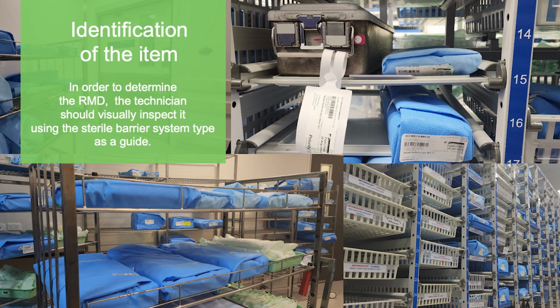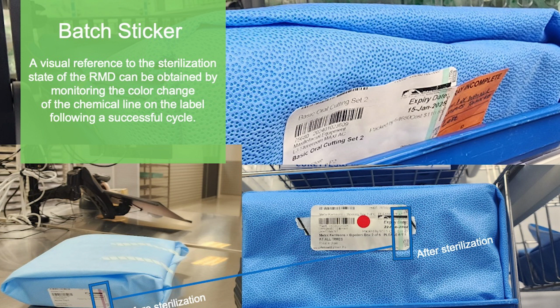In order to identify the RMD, the technician should visually inspect it using the sterile barrier system type as a guide. Batch sticker. A visual reference to the sterilization state of the RMD can be obtained by monitoring the color change of the chemical line on the label following a successful cycle. The label's barcode provides comprehensive set information.